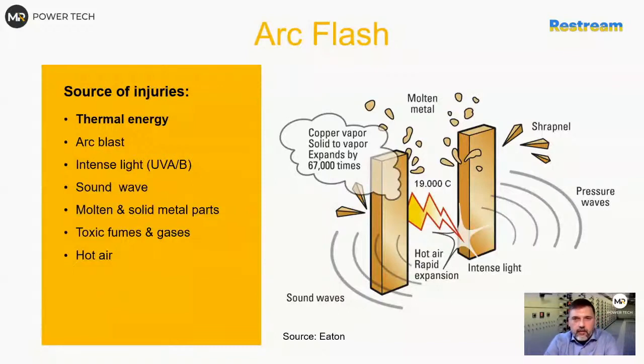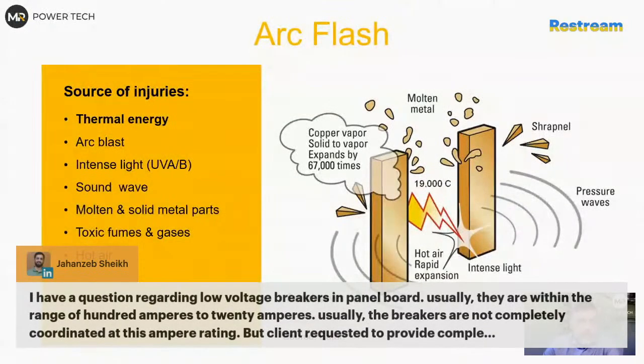So again, I'm kind of guessing now because I don't know what your system is, but if you have to coordinate a full 400 amp with a 20 amp breaker, it's possible, it's quite easy. You might not see it on the coordination charts if you go to the time current curves in EasyPower or other software, because you might see that they are not fully coordinated graphically. But if you have a problem like this, you go to the coordination tables, for example, from Schneider, Eaton, Siemens, ABB. They make a coordination by tests. So they have to test the worst case conditions for two sets of breakers, sometimes for three sets of devices, like fuse with breaker, ACB breaker with MCCB, MCCB with MCB, so miniature circuit breakers that you talk about. And then you can check what is the limit.